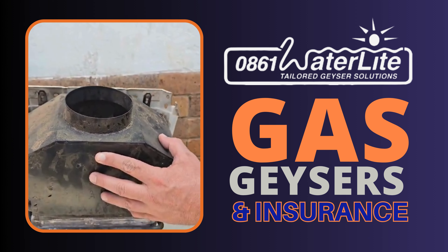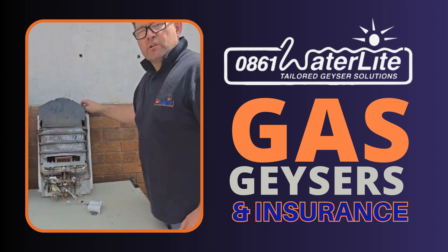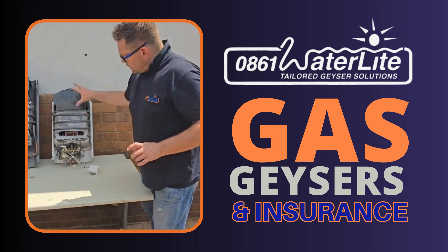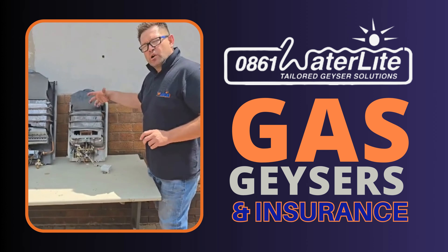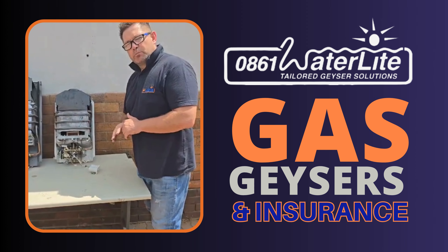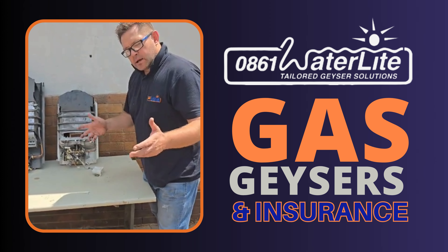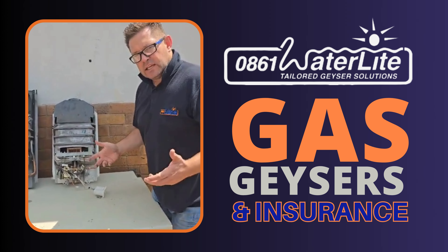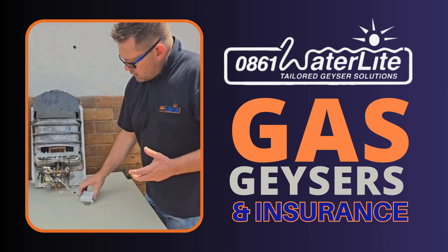The flue acts as a chimney. The angle and position of the flue is critical in terms of functionality, because if this unit can't dispel the heat it stops the functionality of the geyser and limits the performance of the system. I come back to this because the user often thinks 'can't you get it right, it's just a geyser' — but it's not just a geyser.